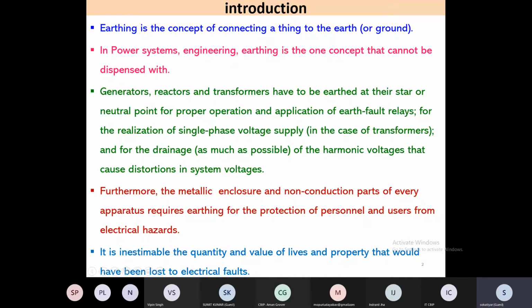There are certain non-linear loads like computers, laptops, and conversion units which convert AC into DC. These types of loads generate harmonics into the system. So these harmonics have to be dissipated to the ground. Furthermore, the metallic enclosure and the non-conducting parts of every apparatus require earthing for the protection of personnel and users from electrical hazards.